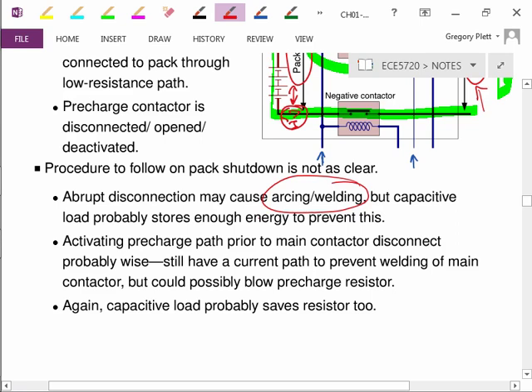It's possible you would want to activate a pre-charge path parallel to the main path before you disconnect the main path. I'm not really sure I know the advantage of doing that, though, because again, the capacitor of the load is already charged to the right level because I'm connected to it. So there's not an obvious benefit of closing the contactor again before disconnecting everything.